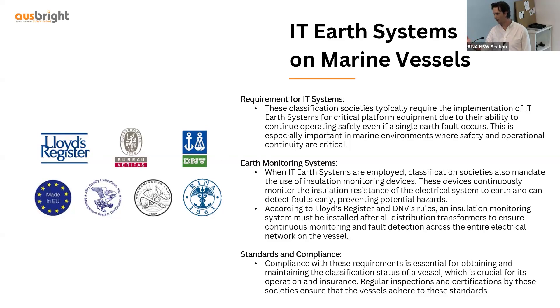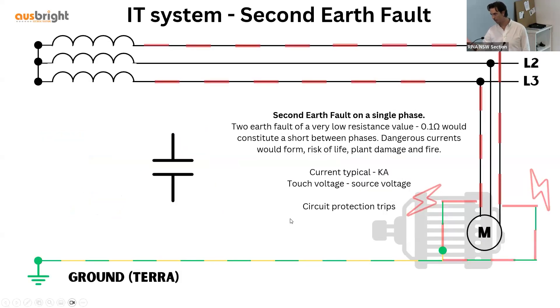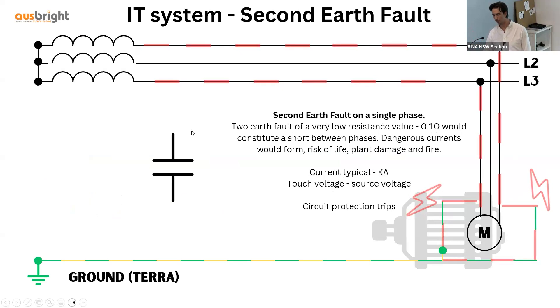Classification societies will say that if you use an IT Earth system, you have to have an insulation monitoring system behind it. The reason is this: you can have one Earth fault, but as soon as you have two Earth faults on a different phase, you effectively have a short between phases, which generates an incredibly high fault current and a very low resistance value. Your plant is going to trip, and your circuit protection is going to operate.